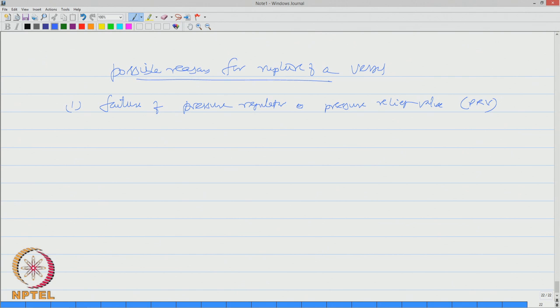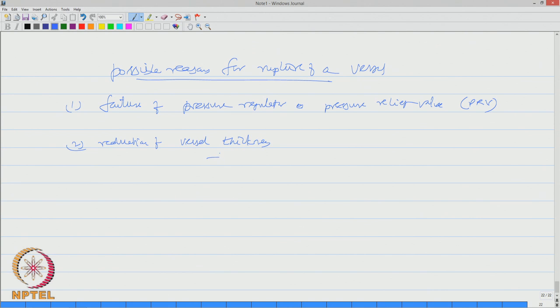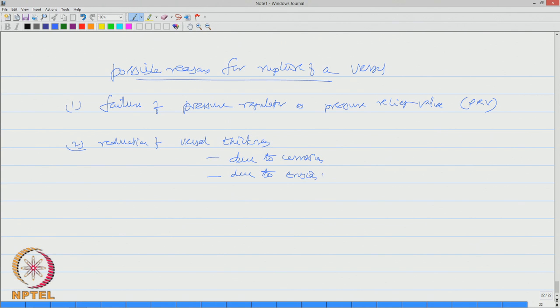It can also occur resulting from reduction of vessel thickness. Reduction of vessel thickness can happen due to corrosion, due to erosion of the wall, and due to chemical attack.